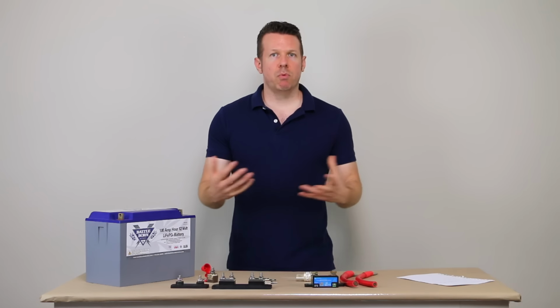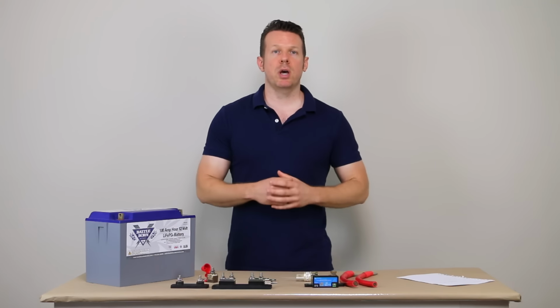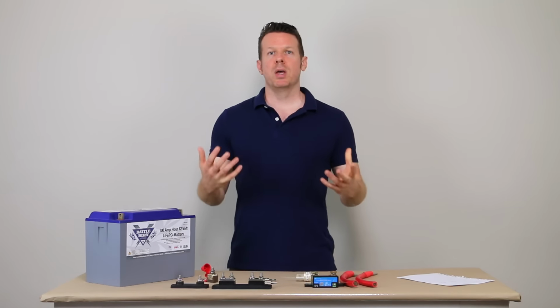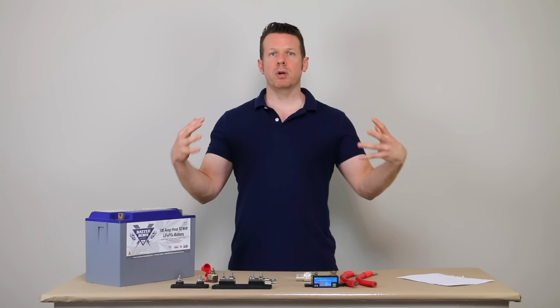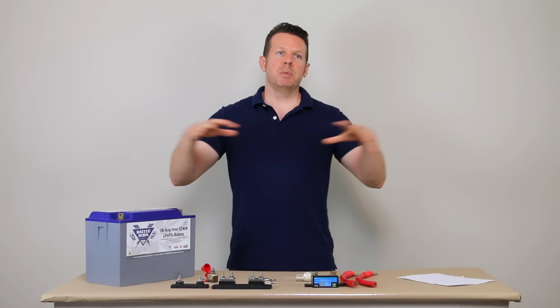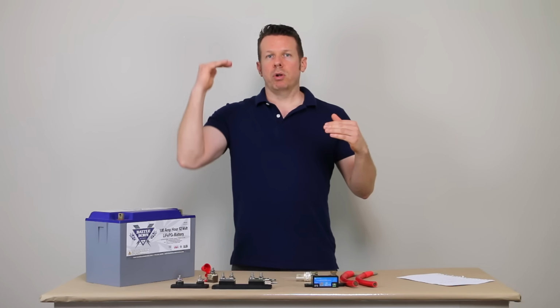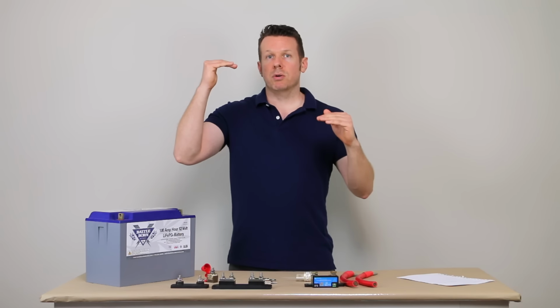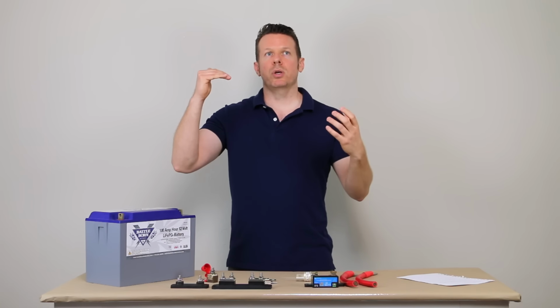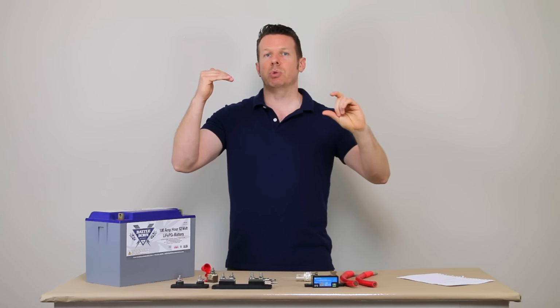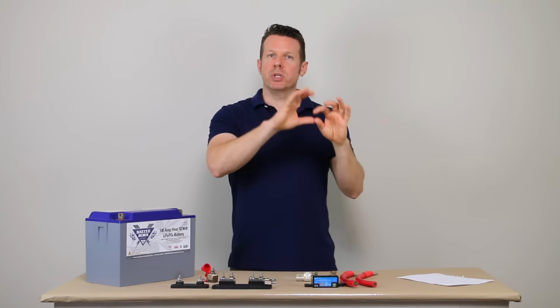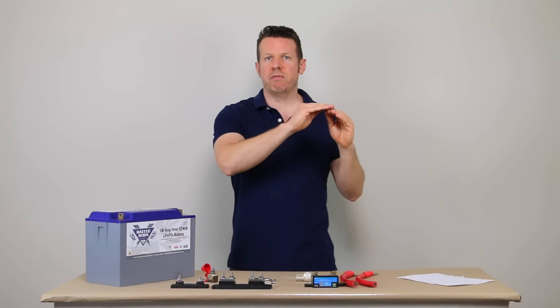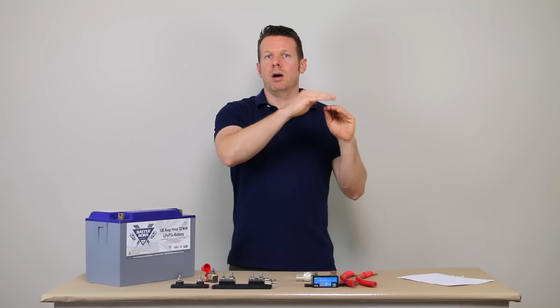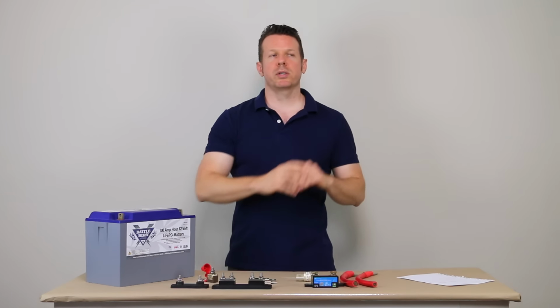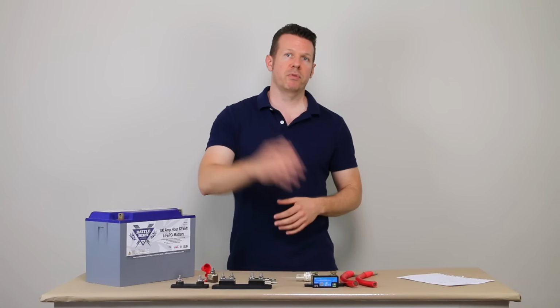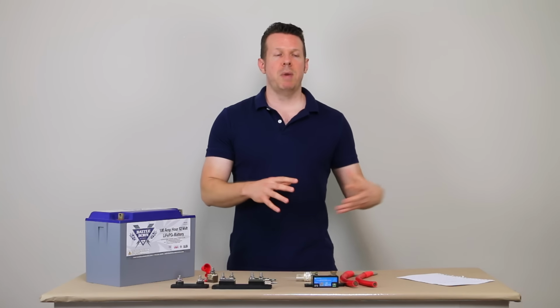So 48 volt is not wrong, but there are implications. The other issue that guy ran into was it was very hard for him to do solar. He had a small Sprinter van with limited roof space, and your solar array voltage needs to be higher than your battery bank voltage. At 48 volts, you're really looking at 52 to 56 volts actual battery bank voltage. With solar, like Victron solar charge controllers, you need 5 volts above the battery bank to start charging, so you're looking at 61 volts coming off the roof to commence charging.